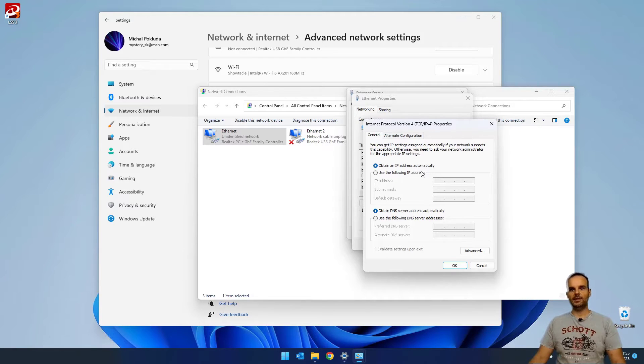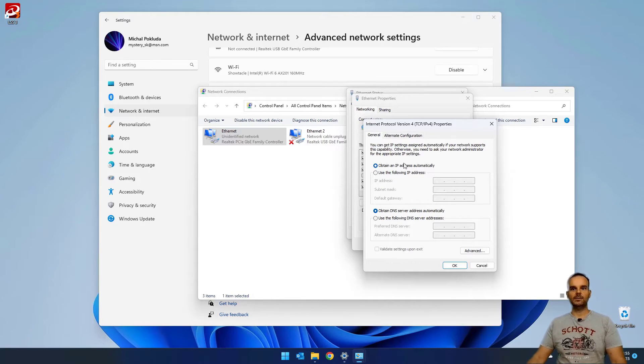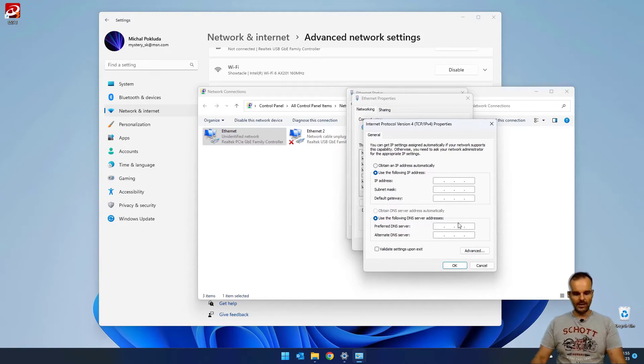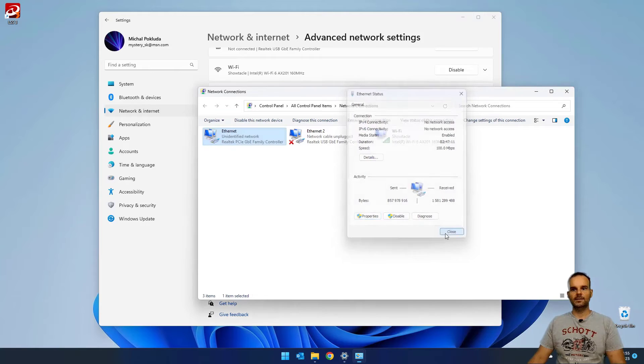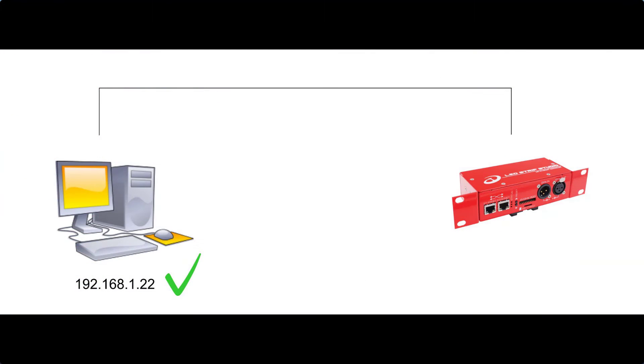We will explain later what that means. But if you want to use your laptop with our devices like LEC3 or Reactivo, we recommend changing it to 'Use the following IP address'. The first three numbers must be the same, and we typically use .22 for the computer. Press OK and now the IP address is changed on your computer.